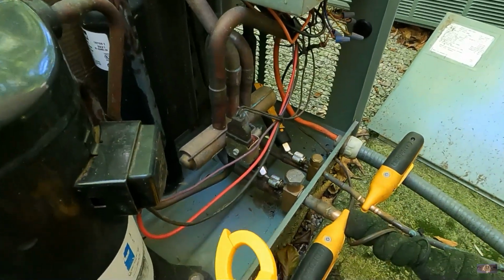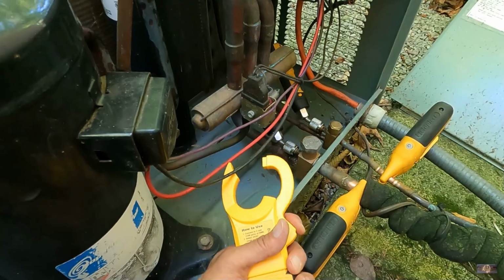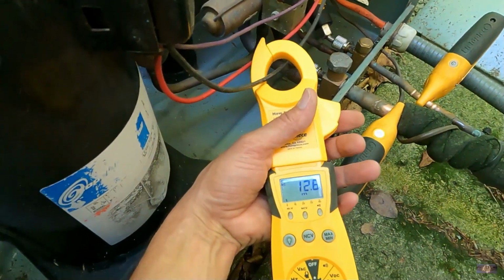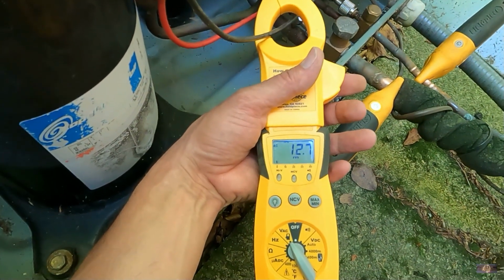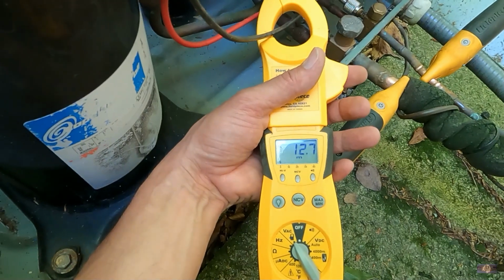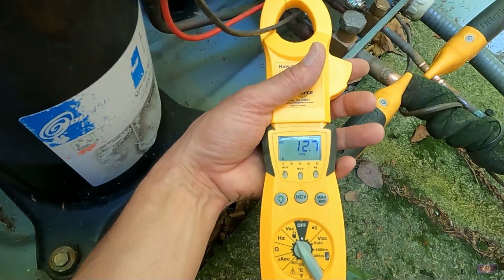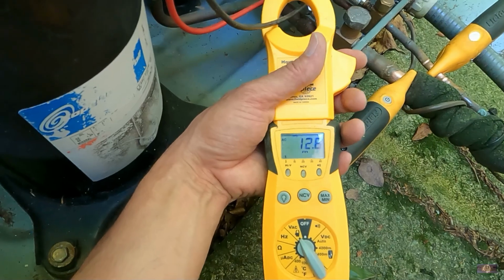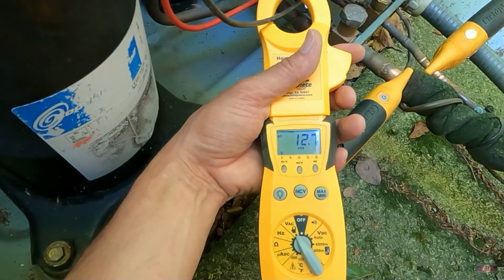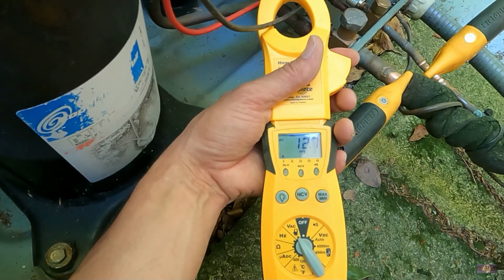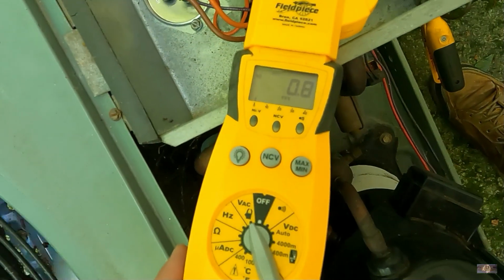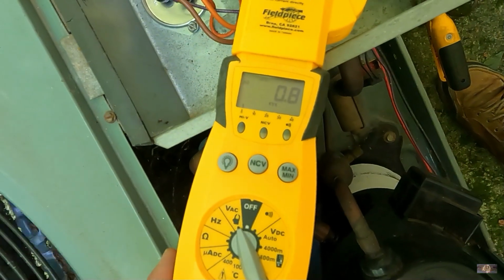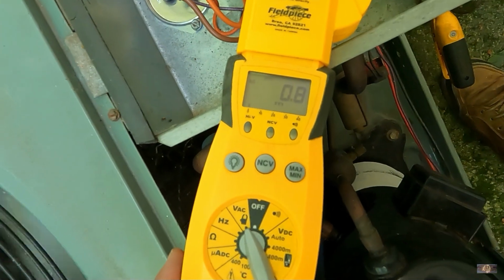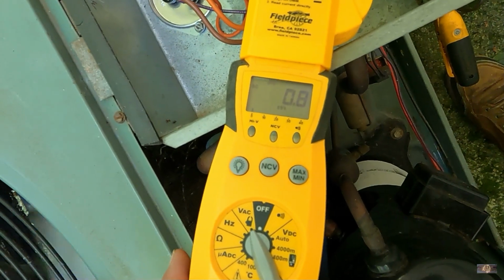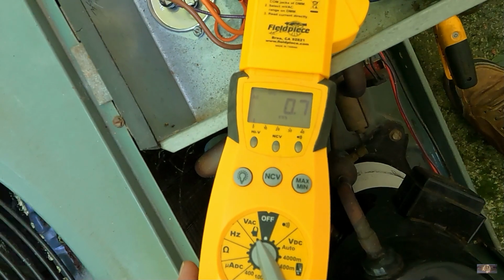Take a draw on the compressor here. And we're pulling 12.7 amps on the compressor. Running load amps is 14.7. This looks like it's going to come down a little bit. 12.6, 12.7. Here's the fan, 0.8 amps. The fan load amps is 0.9, so we're getting on the higher side of that, 0.7, 0.8 amps.